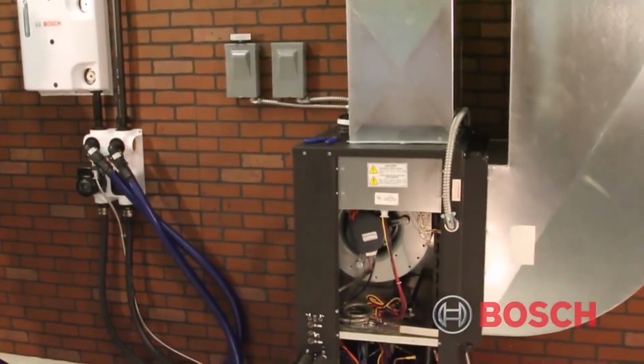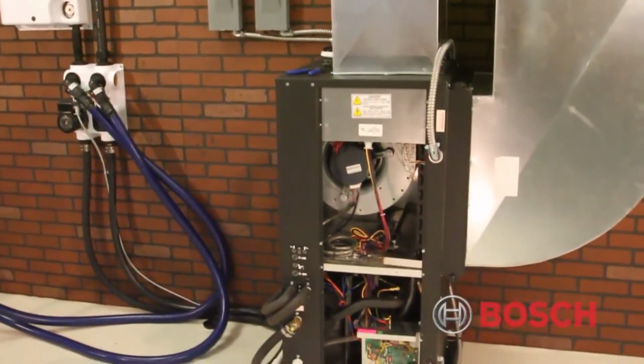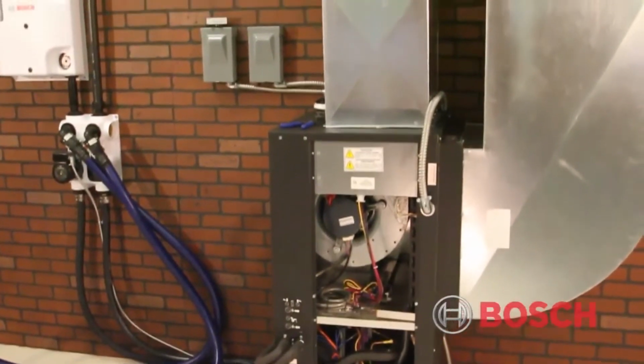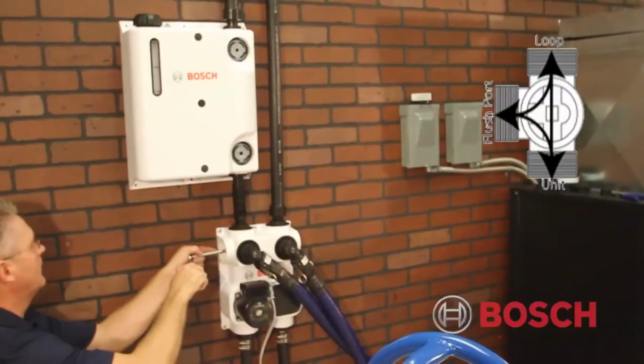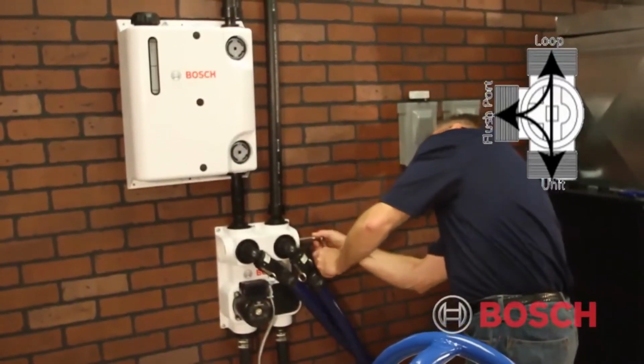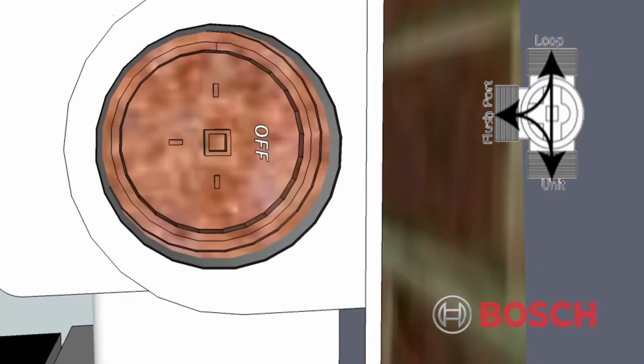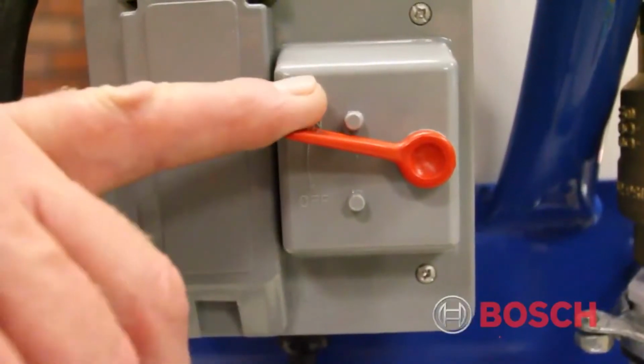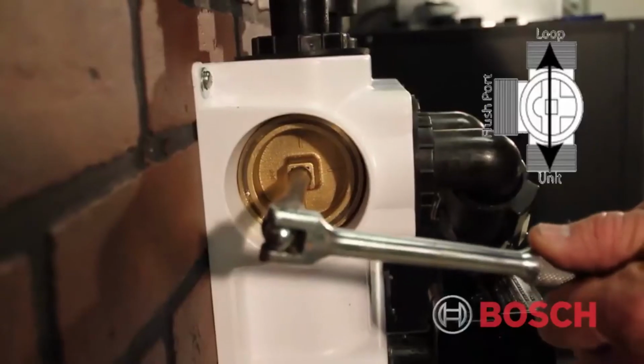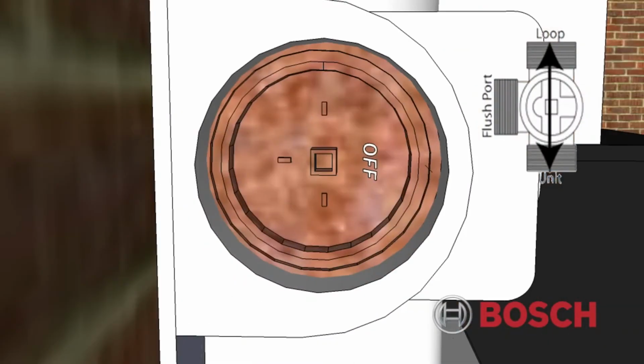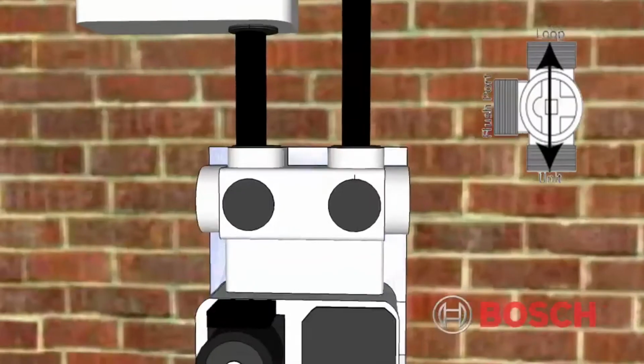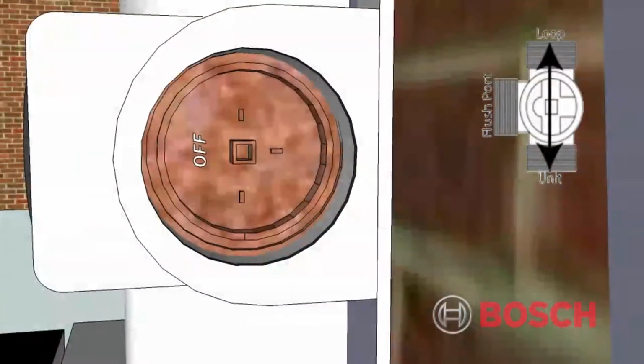Once the air is removed from the unit and the flow center, we now need to flush and purge the ground loop and the unit simultaneously. Starting with the flow center return 3-way valve, rotate the off mark to the full flush position, following immediately with the discharge 3-way valve. In this position, the flush cart purges the air from the unit and the ground loop at the same time. It's recommended to purge the system in full flush position for a minimum of 2 hours. Once complete, turn the pump off and rotate the flow center 3-way valves to the off position starting with the return side. This will isolate the flush cart from the system. Be careful not to pressurize the loop.